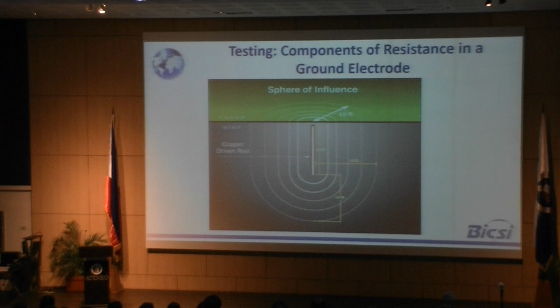So how to test? You have the equipment, grounding, bonding and everything, down to the rod at the bottom. How do you test it? Now, how do you achieve 25 ohms, 5 ohms, 1 ohm, 0.1 ohms?